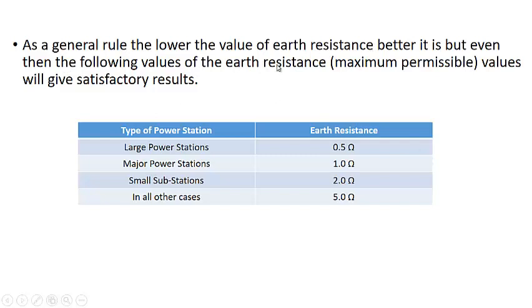We just want that this resistance should be as low as possible, but the maximum values may be there. That means for large power stations, the earth resistance should be as high only as up to 0.5 ohms, and for major power station, that is medium power station, it should be 1 ohm. Small substation, it should be 2 ohm, and in all other cases it should be a maximum of 5 ohms. So in large power stations, the value of the resistance is smaller because the current value is higher, and in that case that current multiplied by this resistance gives some voltage that will be still higher. That's why the resistance should be lower.